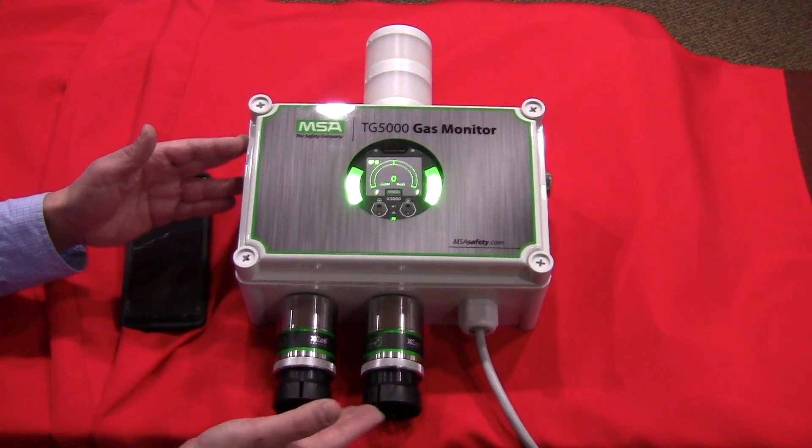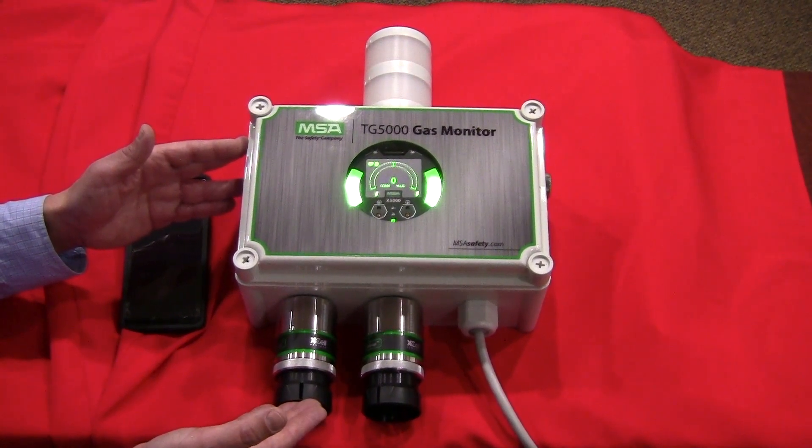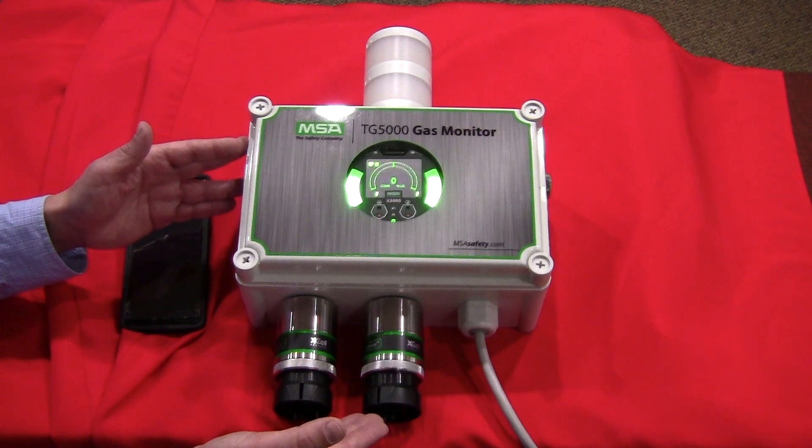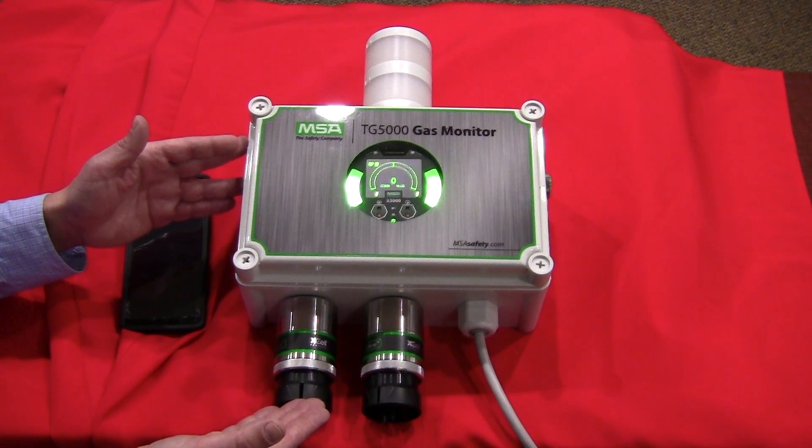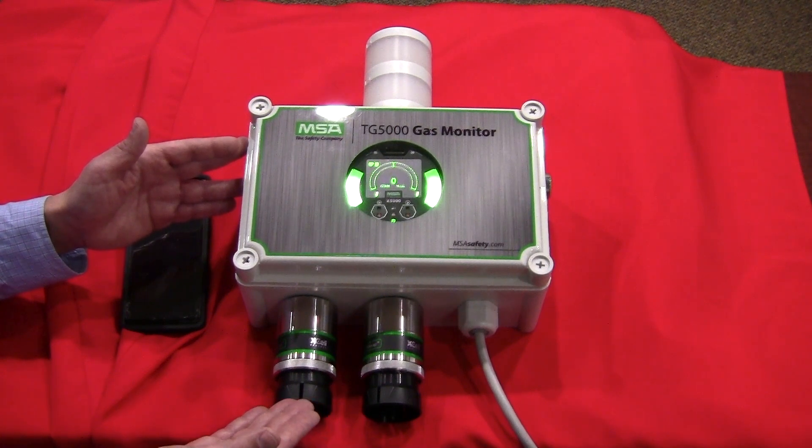I can also do any combination of MSA gas sensors — LELs, CO, H2S, O2 — and you can mix and match gases as required. The sensors are based off the MSA XCell platform, which in the case of our electrochemical cells or O2 cells gives you a three-year warranty on the sensor with a four-year life expectancy. That's even longer for our combustible sensors.